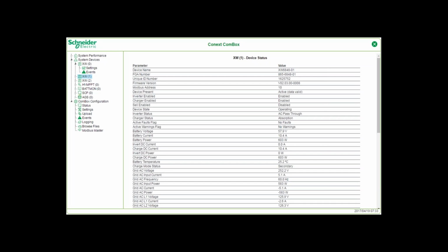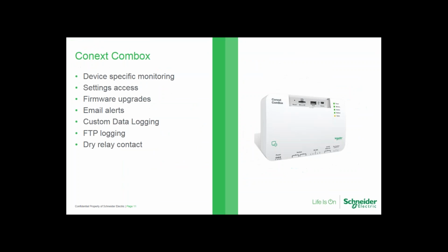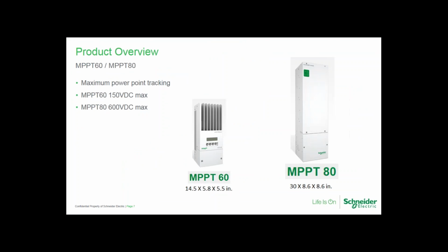All right. And does the MPPT-80 have cooling fins? No. The MPPT-60 is the one that has the cooling fins on the left there. So it's passively cooled. No fan is incorporated in this particular model. The MPPT-80 does incorporate a fan, a single fan that pulls the air up through the bottom and exits out the top. So that's a great question. And so you're looking at two different ways of cooling.